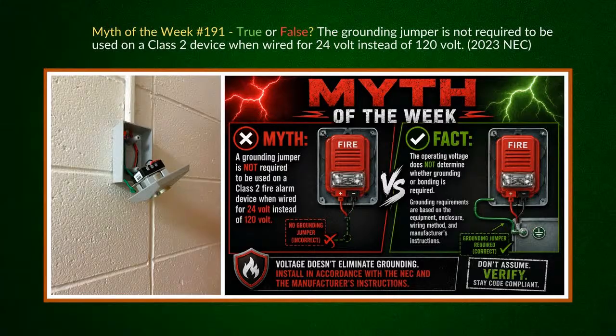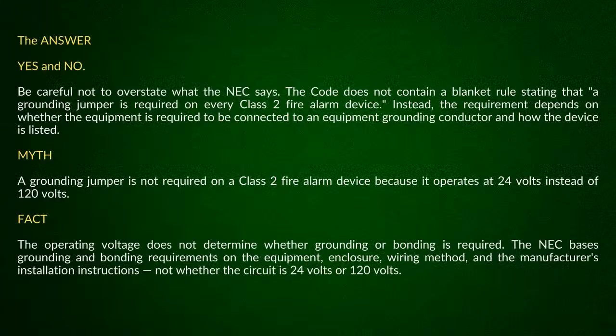Gotcha. Okay. So what I did is I put together a breakdown here. So what is the answer? Yes and no. So you sort of have to look at a couple of different things. I wrote this up because I wanted to be a little careful on the way you look at this. So what I said was, be careful not to overstate what the NEC says at this point. When you look at the National Electrical Code, there's no blanket rule that states that a grounding jumper is required on every Class 2 fire alarm device. That's why I showed the fire alarm, because it depends on the way it's established and the way the wiring methods are set up.